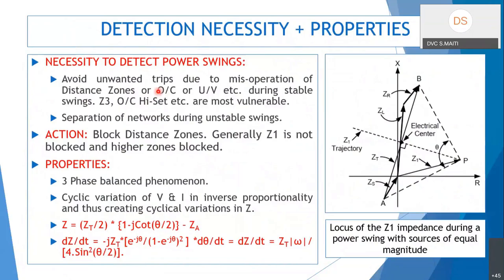During a power swing, the impedance fluctuates and may enter zone 3, zone 2, or even zone 1, which could cause tripping even during a stable power swing. We don't want the power system to trip due to relay misoperation for stable power swings. In general, during power swings we do not want our network to trip unnecessarily.